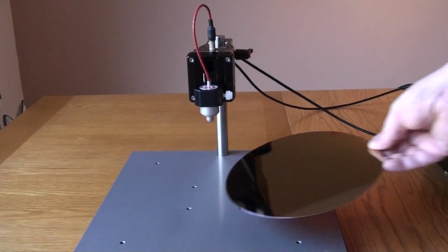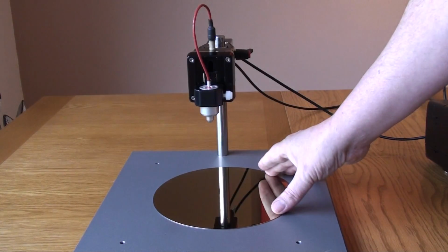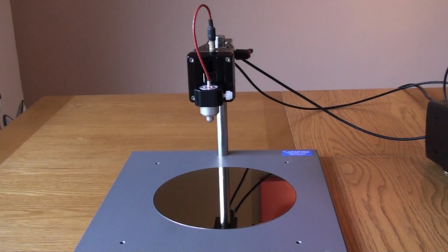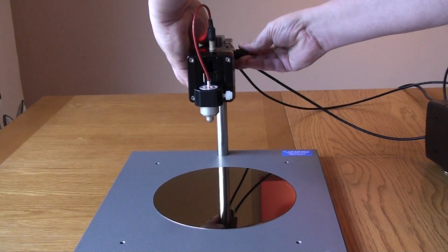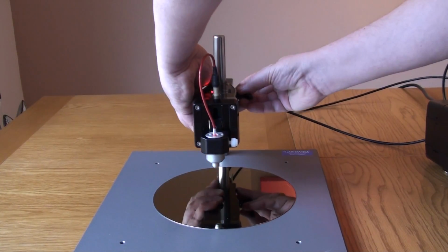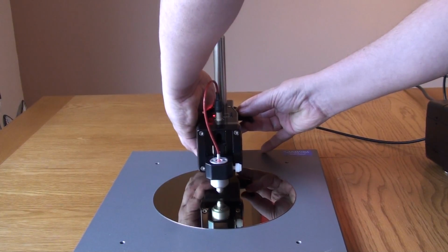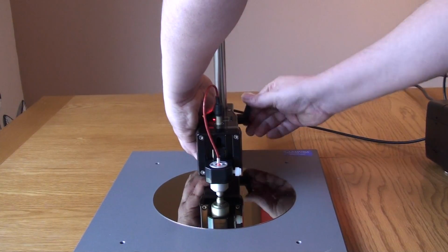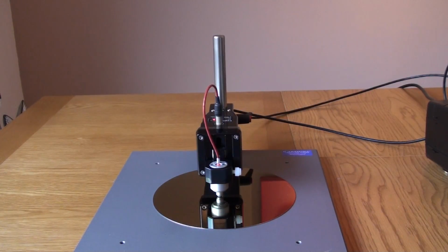Place the sample to be measured beneath the mechanism and lower the whole mechanism so that the needles just touch the sample and do not compress. To get the optimum loading, we now move the probe head so that the insulating pad is actually touching the sample. At this point, the needle load is at its optimum level.